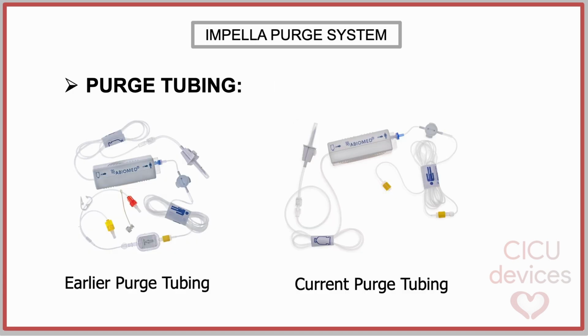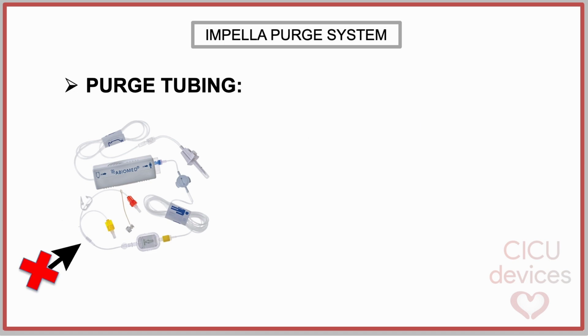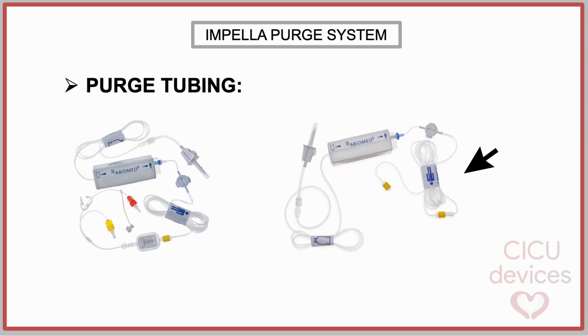From the cassette, purge tubing carries the fluid onward toward the catheter. The purge tubing is a thin plastic tubing that connects the purge cassette to the components of the purge unit. Of note, in its early designs, the purge tubing incorporated a Y-shaped extension that connected both the arterial lumen and the purge lumen. Beginning with the Smart Assist models, this Y extension was required to be discarded during the initial system setup.